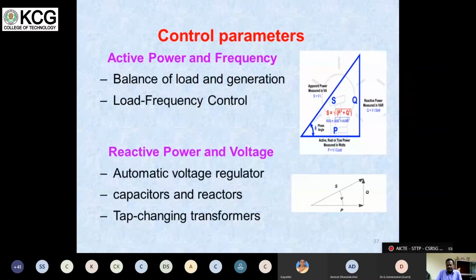Both power is generated from the generator. Active power is the useful power, and reactive power is the magnetizing power. Most of our load, more than 80%, is inductive load. Inductive load means motors, fans, etc. An inductive load cannot be started without reactive power. So reactive power is required for continuous operation. Active power is also required.